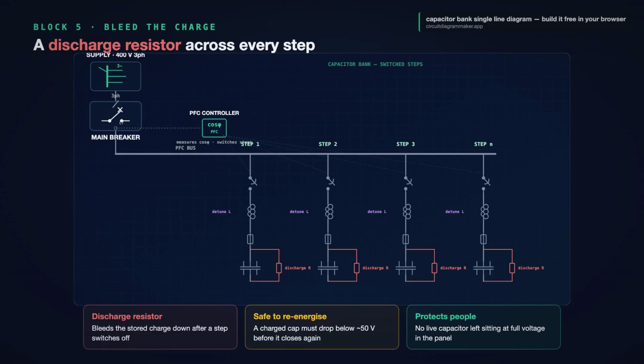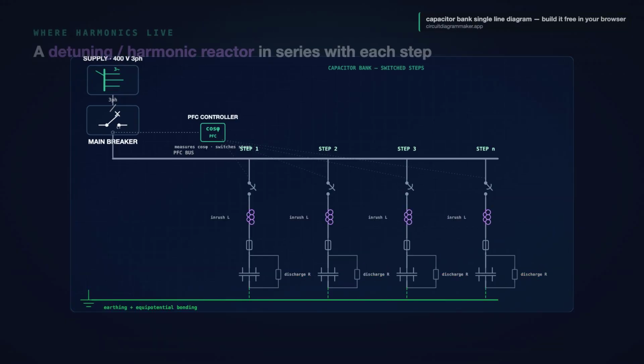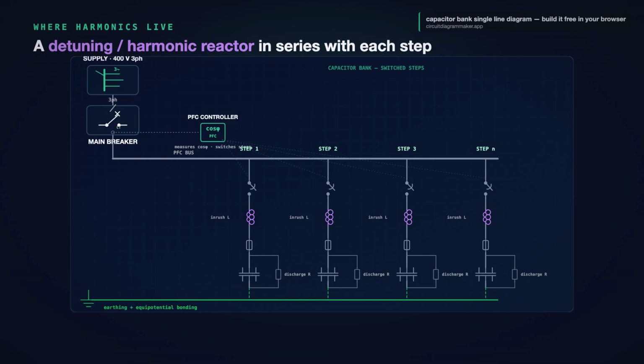Its only job is to slowly bleed that stored charge away after the step opens, pulling the voltage down below a safe level, typically 50 volts, before the contactor is allowed to close again. It protects the people who service the bank, and it protects the caps from being switched onto a residual charge. Draw the discharge resistor every step.